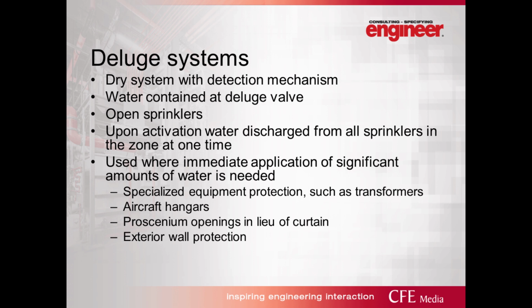I won't spend much time on deluge systems. These are basically just dry systems with a detection mechanism, but all of the sprinklers, instead of being closed sprinklers that have to activate one by one, all of the sprinklers in the system are open. Upon activation of the detection mechanism, the deluge system valve opens up, water flows into the piping and flows out of all the sprinklers that are a part of that system.